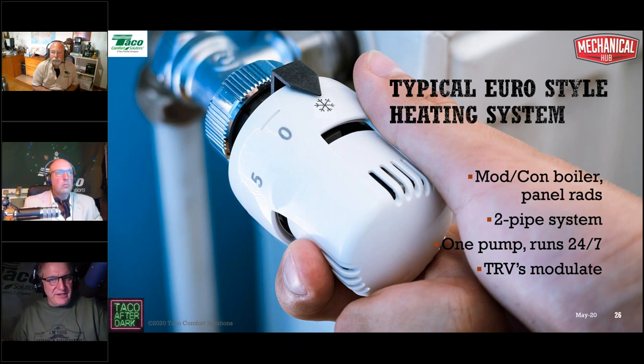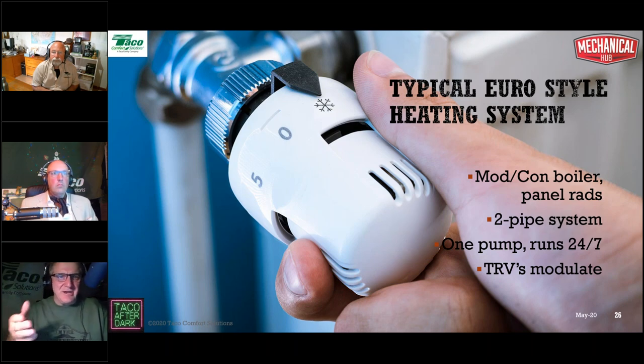It eats up electricity. The reason they do it is they don't use thermostats. They don't have a thermostat on the wall that tells the boiler to fire or the pump to fire. All right, the pump runs all the time. The TRVs modulate to control the temperature in the room or the comfort level in the room.